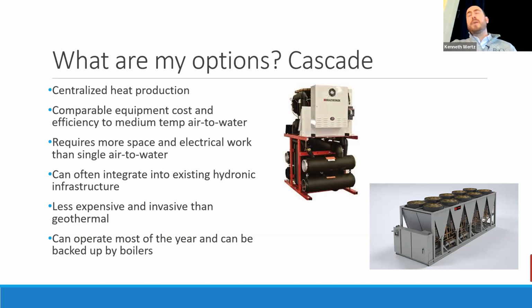Well, you can use a second heat pump that can generate a little bit of heat, and then it can be boosted by the second heat pump. We would call that a cascade system. And again, it's more efficient. It's more likely to be able to keep up with the building load. But now you've got two heat pumps that you need to maintain. So twice the cost in terms of maintenance, electrical, space, piping, et cetera. But the efficiency difference we'll talk about is potentially enough to make it worth exploring this option.